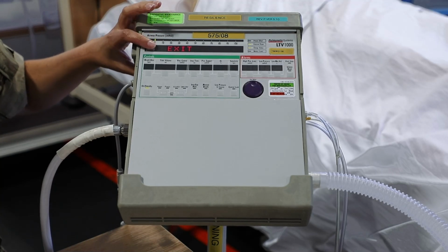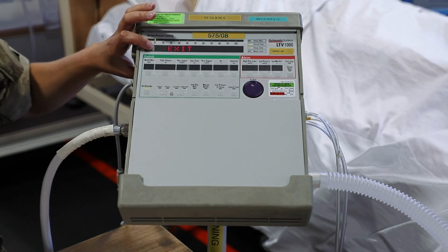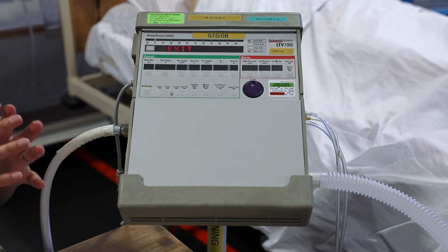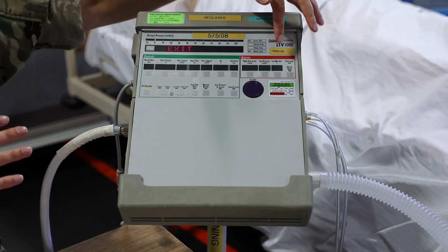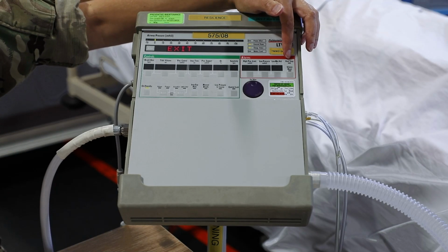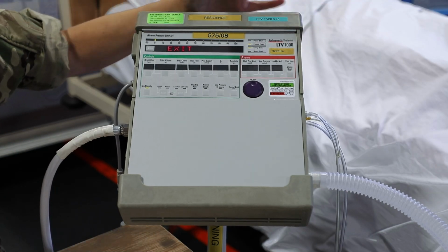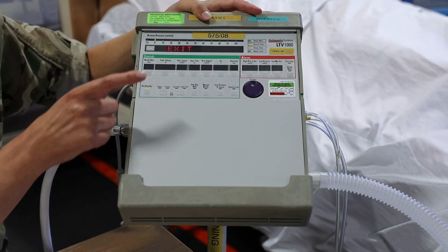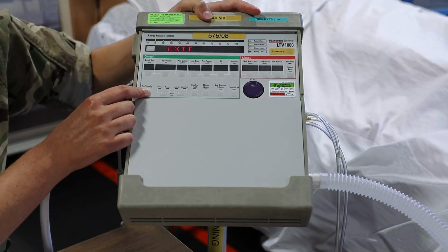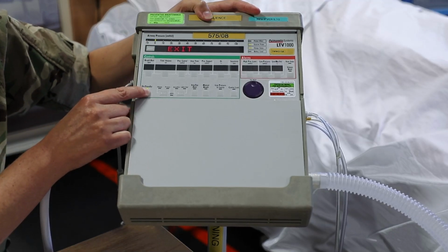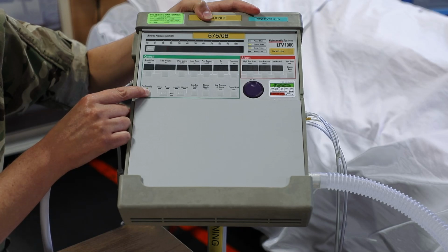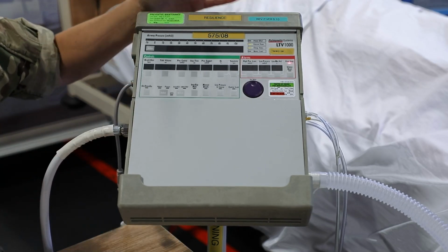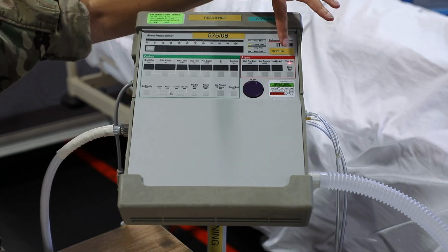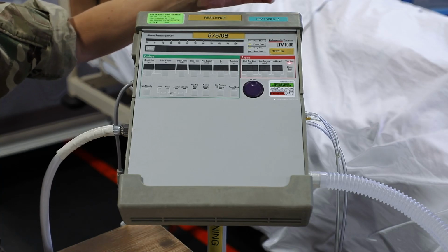Pressing select again takes us into the exit, and at this point we need to remember to switch off the LTV altogether, because that's going to confirm that our vent in-op light works and that the alarm works as well. So this can be a reminder to switch off the whole of the LTV. So press and hold on. You can hear an alarm and you can see that vent in-op light has become visible.